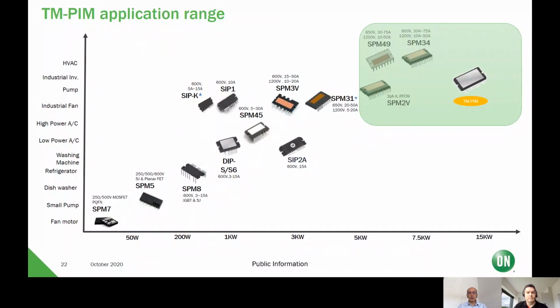It makes sense to make the PIM portfolio for high power. PIM are for more high power, so we'll cover the range of 5 to 20 kilowatt motors in industrial applications. I think for consumer we'll stay with smaller modules because they have smaller power motors, and it's a much cheaper and easier solution. PIM is in the middle in terms of complexity because you have the driver externally, but it allows perhaps more flexibility in terms of handling the EMI and the efficiency. So that's why the PIM, the transfer mold PIM range will be for the high power.